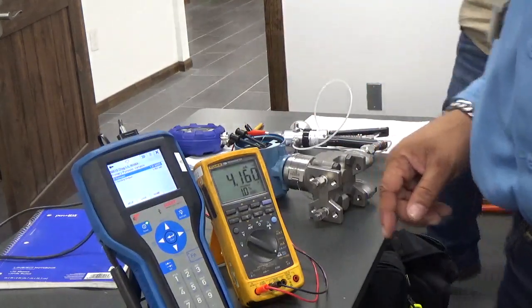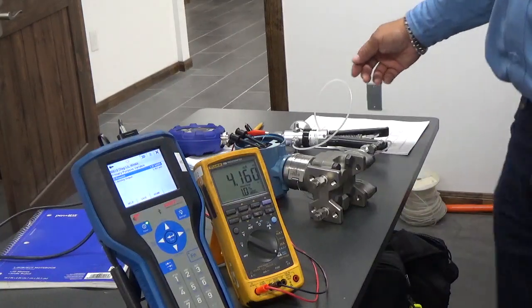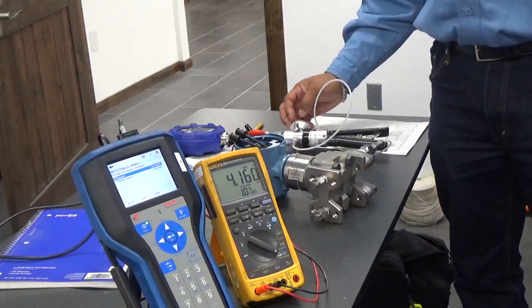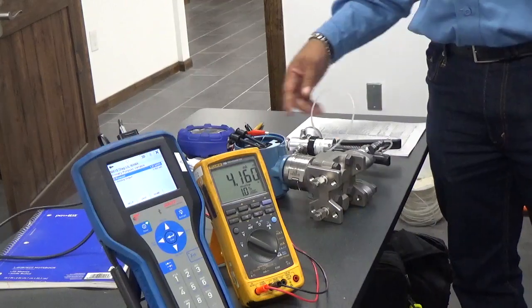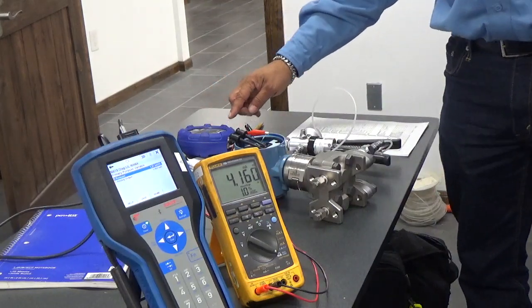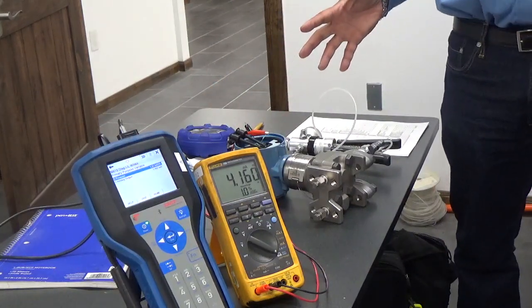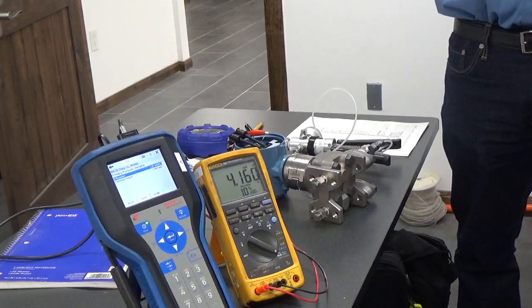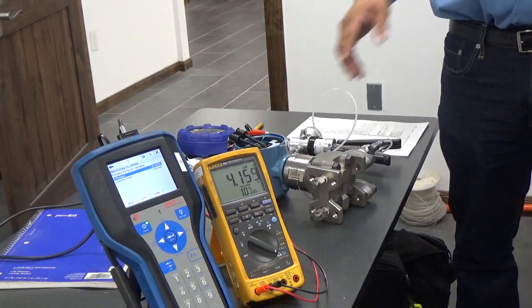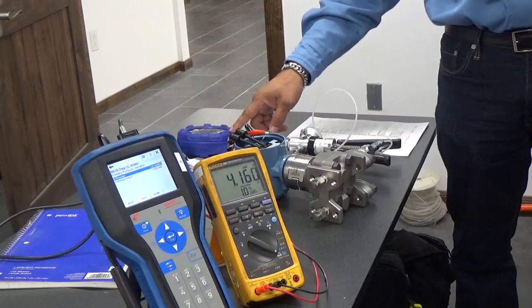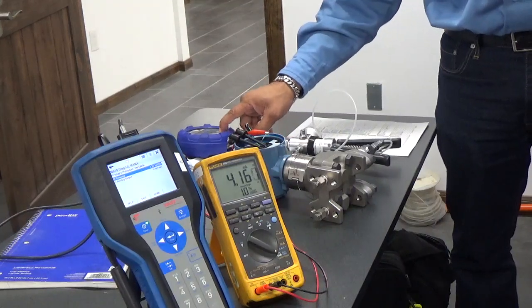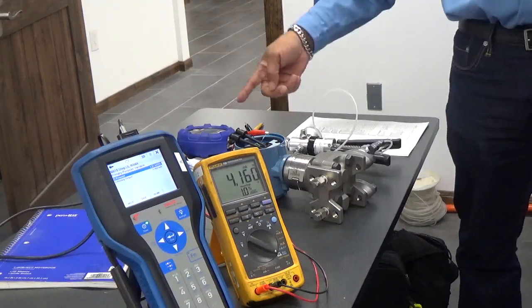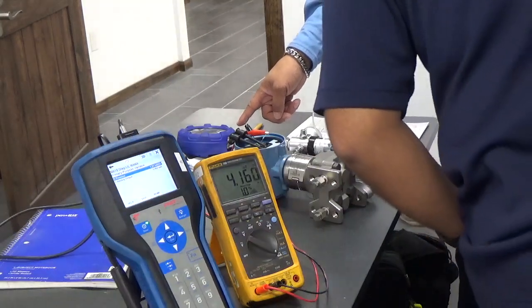So whenever I have this opened up right here, what that tells me right away is that it's opening up to atmosphere, so there should be 0 pressure on the transmitter, right? But this is reading 0.2. So what we would do is just push it right here, and it would zero it out. You see it?